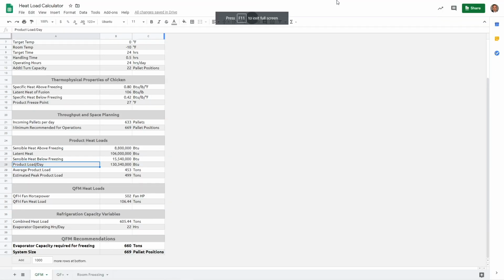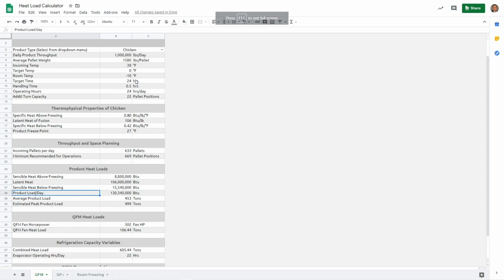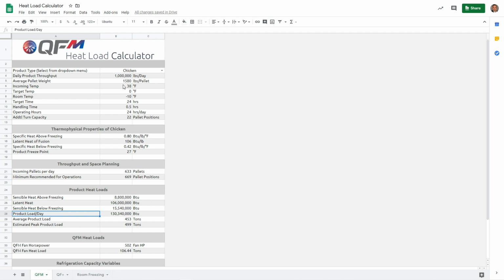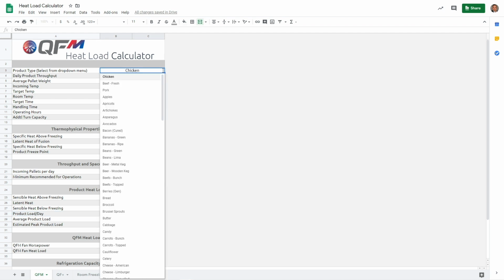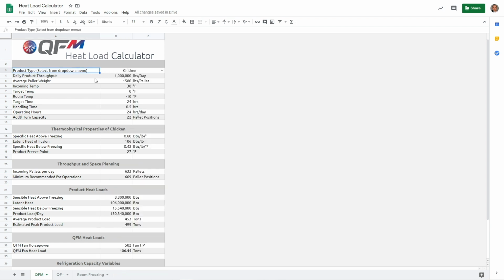So we'll then use this information to input into our heat load calculator. We have just another spreadsheet. The first entry, we said it was chicken, but notice we have a pull down menu and we have every kind of product we've run up against. So that has lookup tables for all the thermophysical properties. So we input our chicken, then we look at the million pounds per day throughput. We input our average pallet weight. In this example again is 1,580 pounds per pallet.